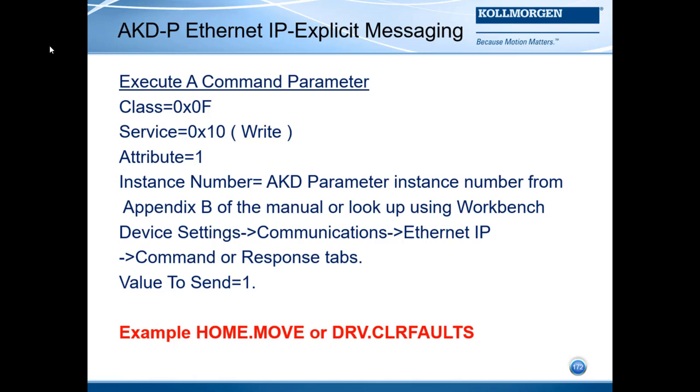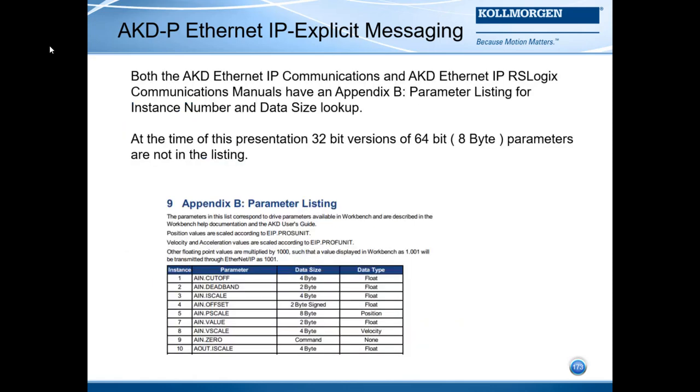An example of a command parameter would be the home.move or the drive.clearFaults, or CLRFAULTS. Both the AKD Ethernet IP Communications and the AKD Ethernet IP RSLogix Communication Manuals have an Appendix B for parameter listing for the instance number and data size lookup.